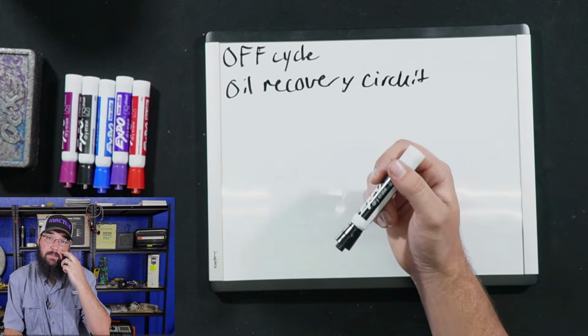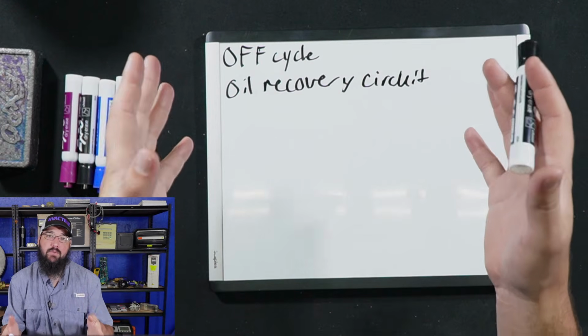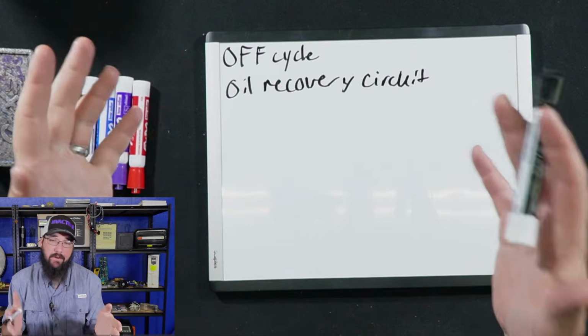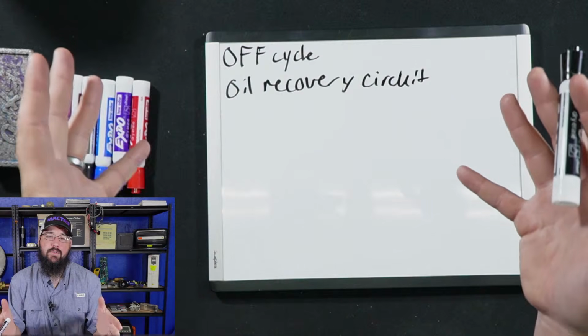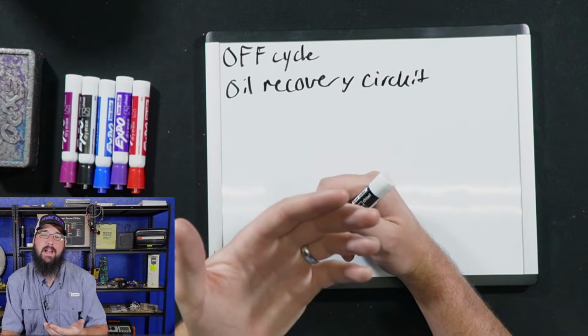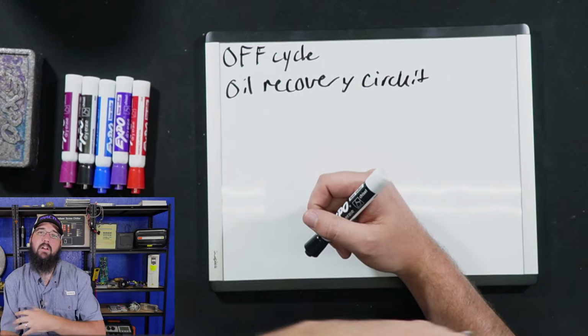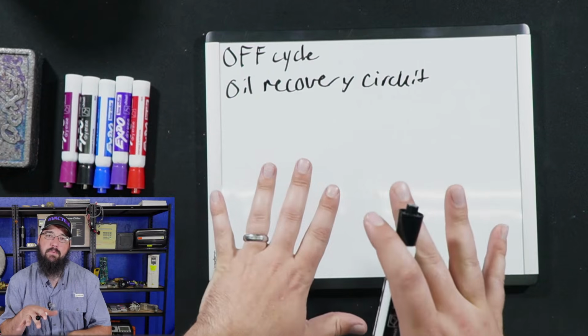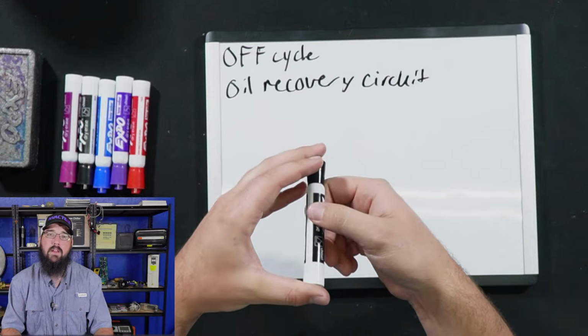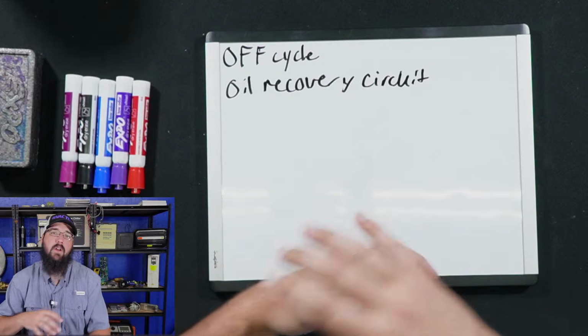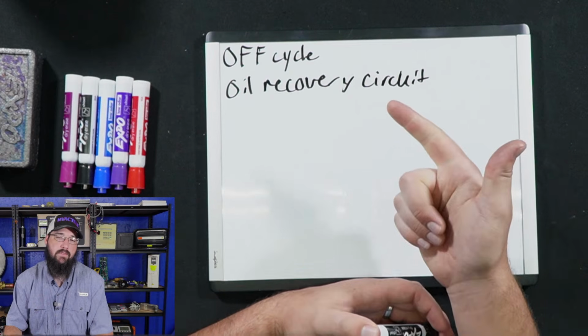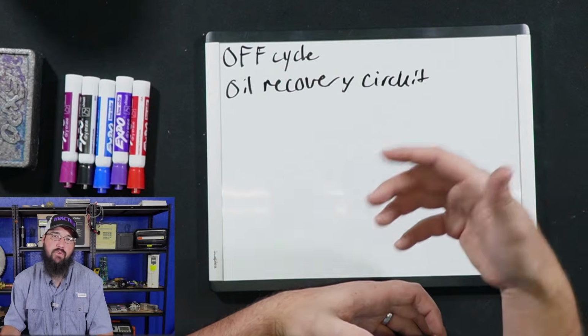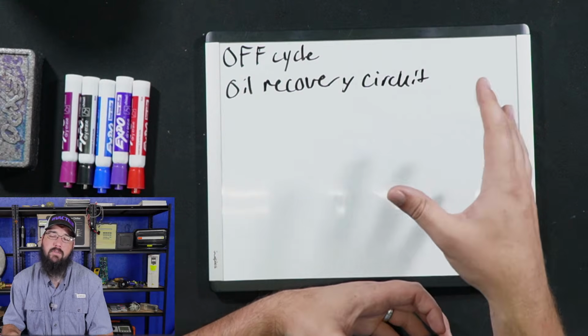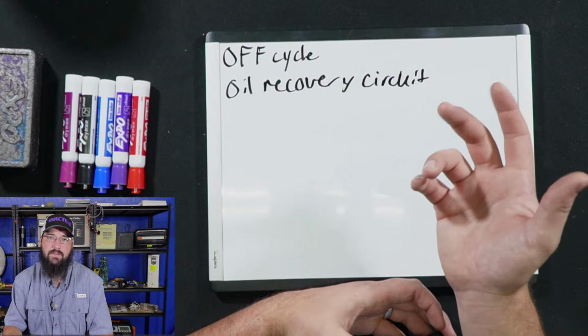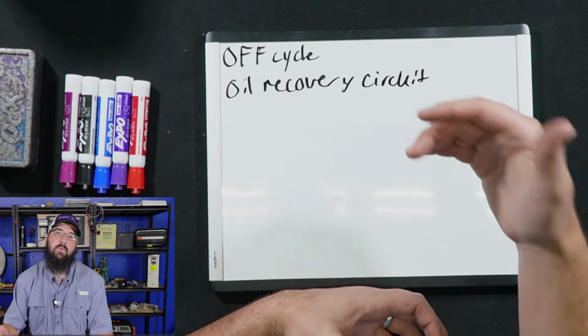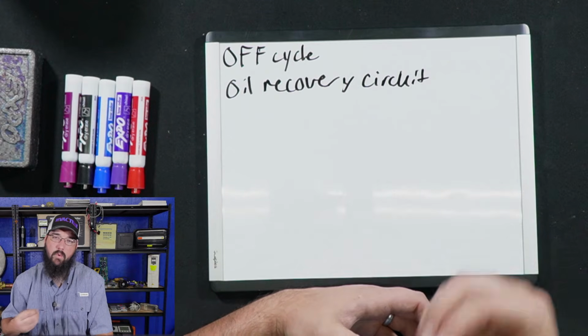If we get too low of a DP across the machine, and by DP I mean differential pressure between the evaporator and condenser, we need that differential in order to help facilitate that oil return and to get enough discharge gas pressure to come back through and hit that eductor block and pull it back out. So having a high enough DP across there is important in order to get that oil back. Now, all of this is just assuming we're discussing a flooded or falling film evaporator. If we're talking about a DX style shell and tube or a braze plate, it's a much simpler process. There's less involved there. For those, it's just strictly about velocity. But for flooded or falling film, this is where we have all these extra variables and trying to manage getting that oil back out of the evaporator.